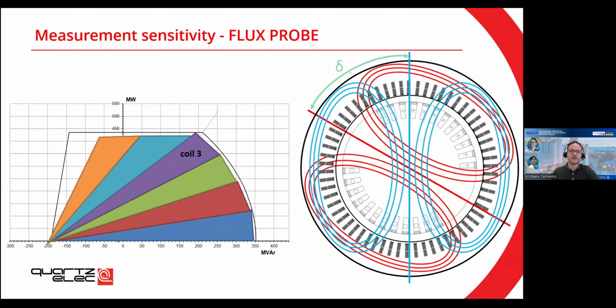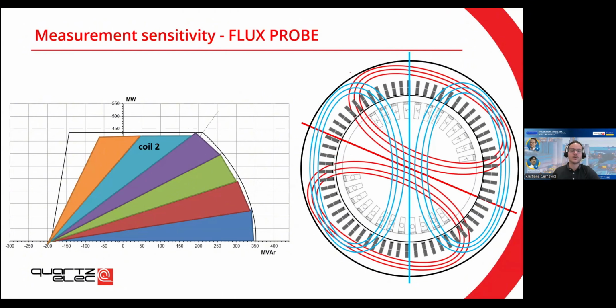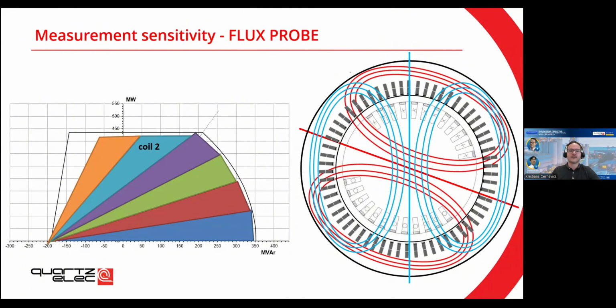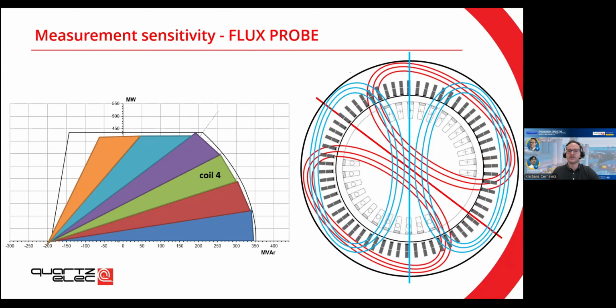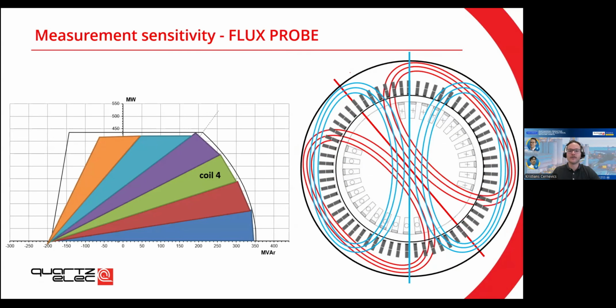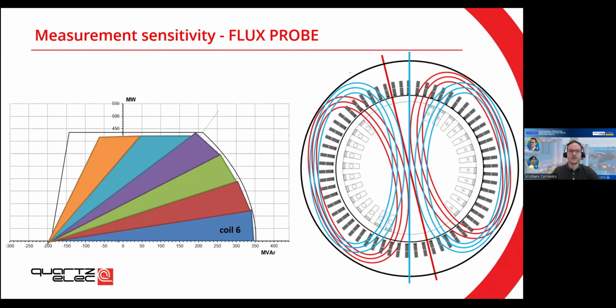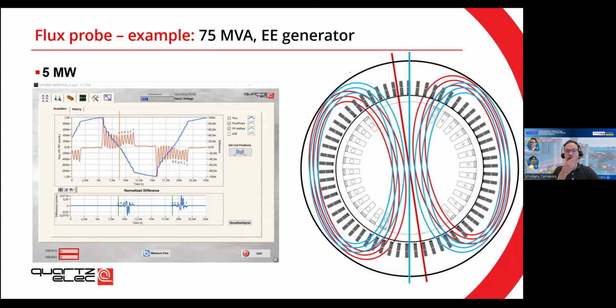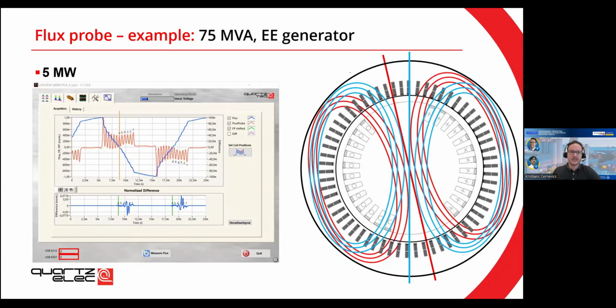To give you an example, here you can see the graph of the active load versus reactive load. At different points, a different coil will be more sensitive for measurements. Once the load is here, you uncover, for example, coil number 2. Once the load is increased, you will uncover coil number 4, and so on. To give you an example also of how it looks in the software, here it is on the generator with an initial load of 5 megawatts. So there is a small phase angle. And what you can see here is that the orange line is going through coil number 6.